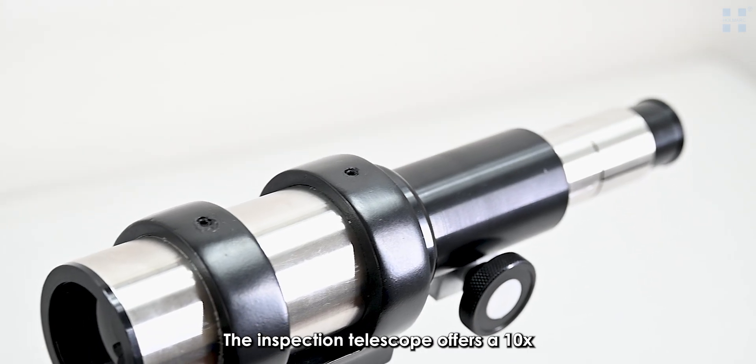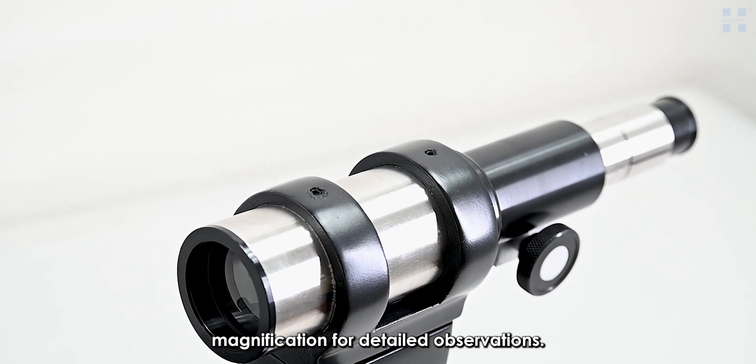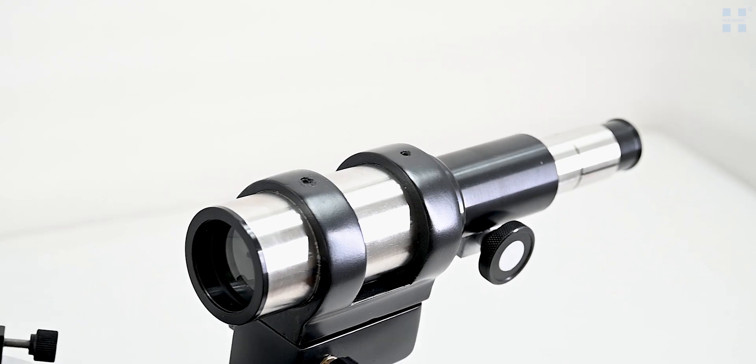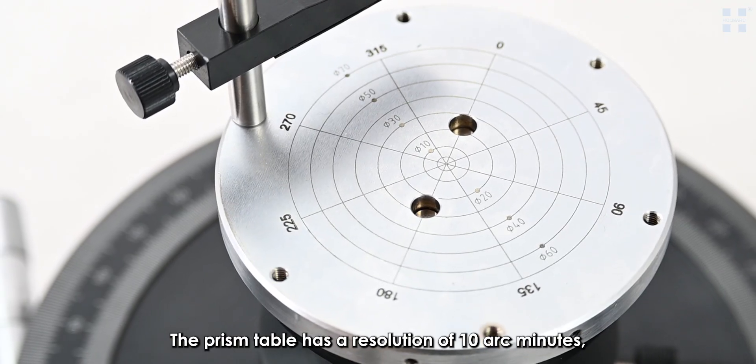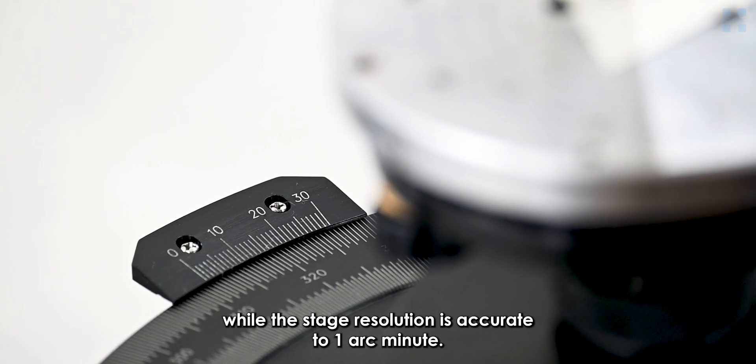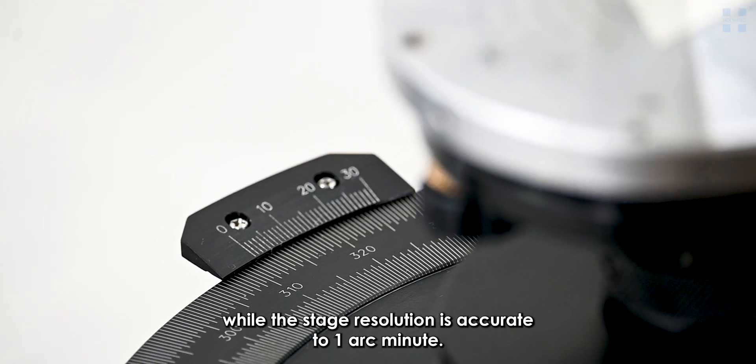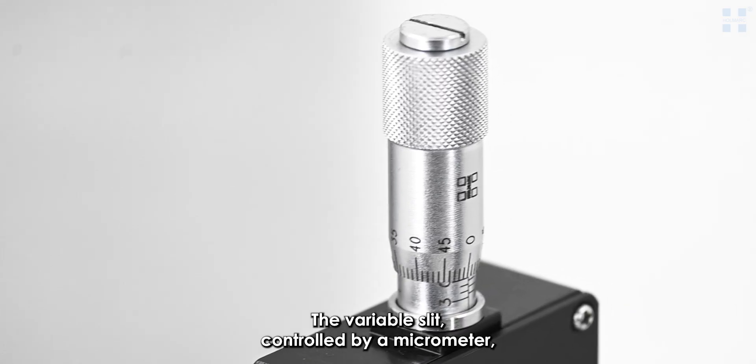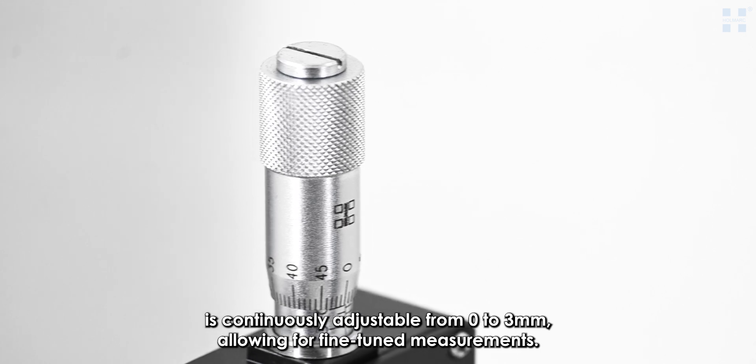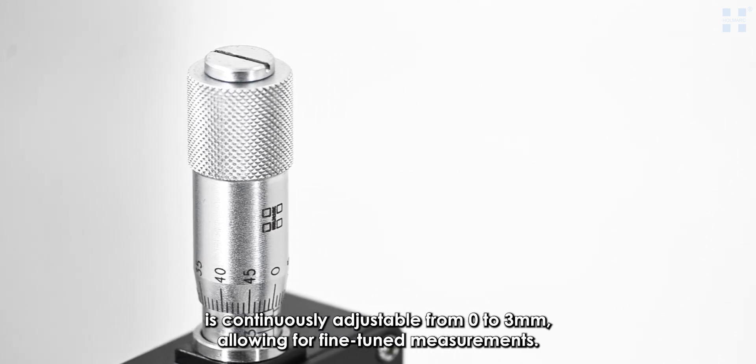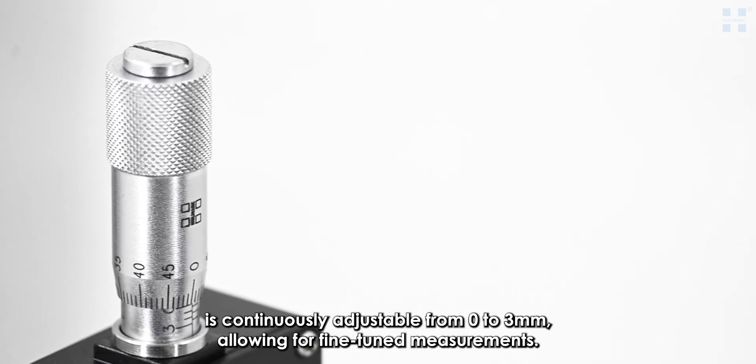The inspection telescope offers 10 times magnification for detailed observations. The prism table has a resolution of 10 arc minutes, while the stage resolution is accurate to 1 arc minute. The variable slit, controlled by a micrometer, is continuously adjustable from 0 to 3 mm, allowing for fine-tuned measurements.